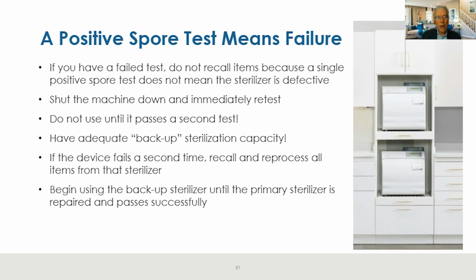Don't use it or the instruments from it until that second test shows it's working. That's why you want adequate backup sterilization capacity. That's what I like about this picture, it shows two M11s, Midmark M11s. It's really important to have excess capacity, so even if one machine is down, you can continue to do business.